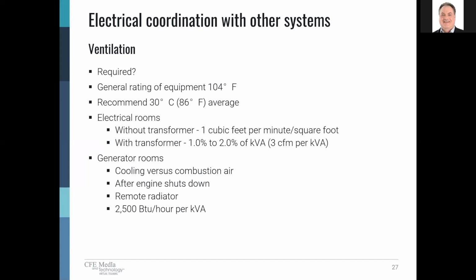Understand what happens after the generator shuts down and continues to cool, using temperature sensors, and use an average rule of thumb of about 2,500 BTU per hour per kVA rating of the generator in the early stages of planning for generator rooms. Later on, you're going to want to bring your vendors in for a sit down between you, the mechanical engineer, and the generator vendor.